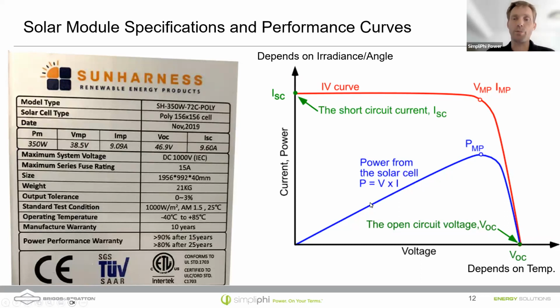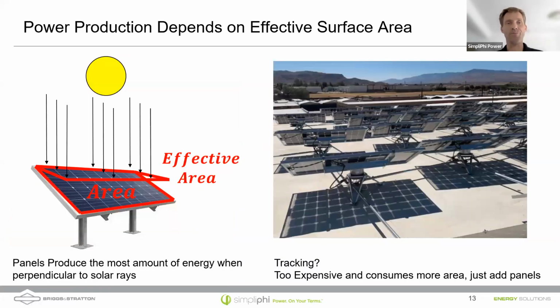This blue curve is showing you power, which is the current times the voltage across the panel - the current through the panel times the voltage across it is the power you're getting out of the panel. As I increase my voltage and my current, I'm going to get the maximum power point. So if I follow the curve of my panel and start putting more resistance, more load on the panel, I'll get less current. Eventually the current starts to drop down, but I'll reach a maximum where current and voltage product is maximum. That's known as the maximum power point, and the equipment is supposed to track that.